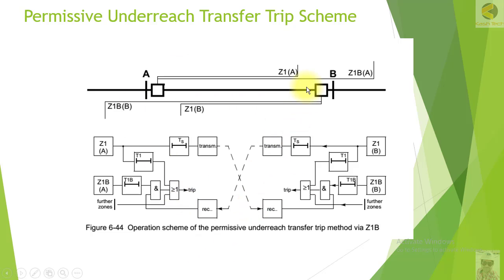For example, if there is a fault near Station B, this breaker will trip immediately — the local breaker in Zone 1. At the same time, it will send a permissive signal to the remote Station A indicating that a fault has been seen in Zone 1 and that the local breaker at Station B has tripped, and that Station A should also trip.